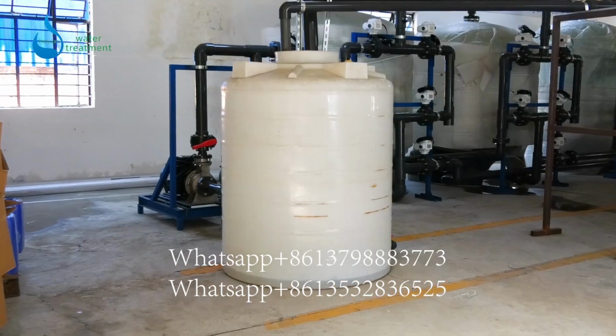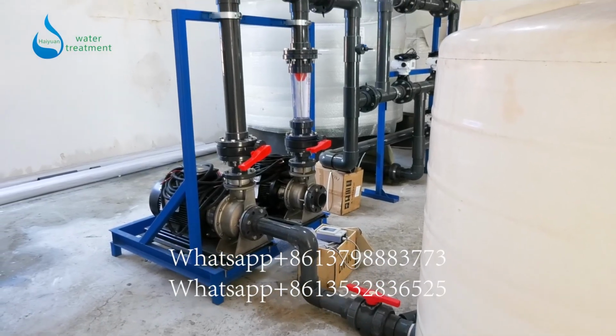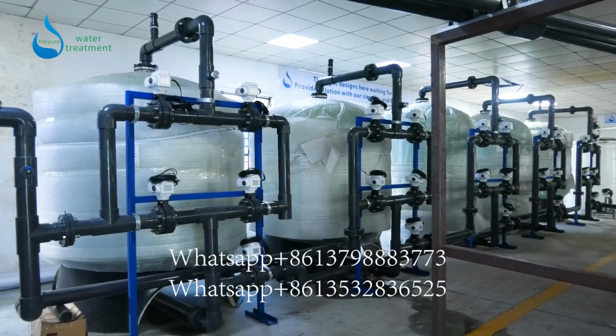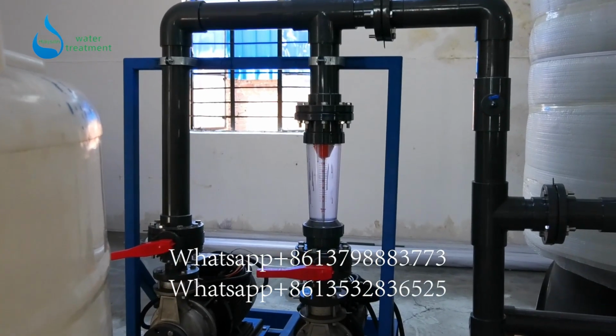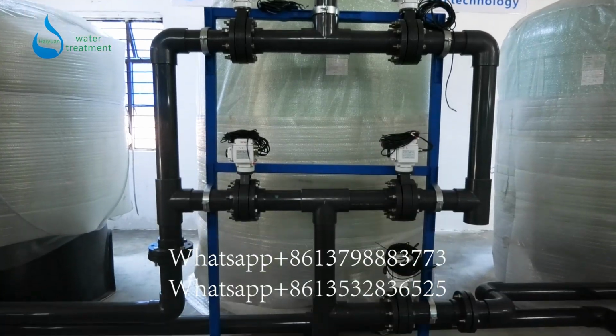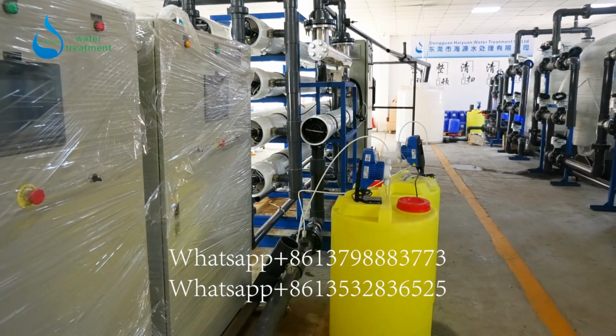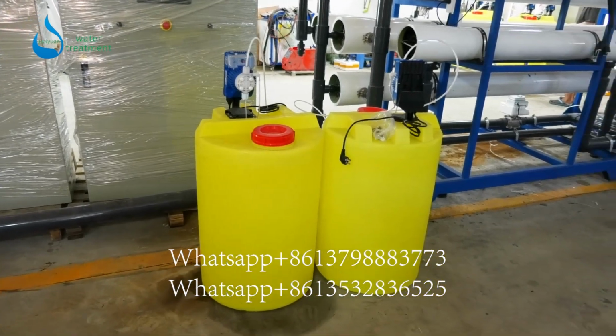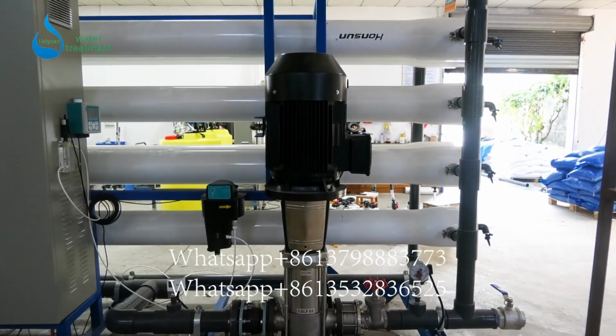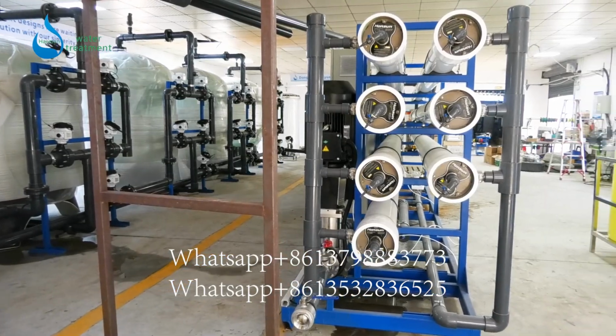This is an industrial reverse osmosis plant producing water for shampoo. The process flow includes chlorination device, raw tank, boosting pump, quartz sand filter (2 in parallel), activated carbon filter (2 in parallel), water softener, anti-scalant dosing device, SMBS dosing device, precision filter, high pressure pump, RO, UV, tank. All valves are electric butterfly valves to achieve automatic operation and backwashing functions.